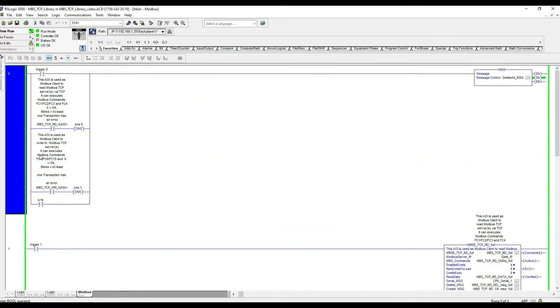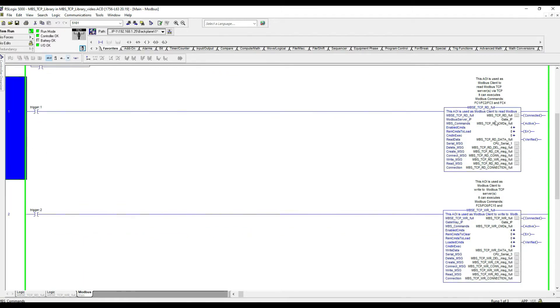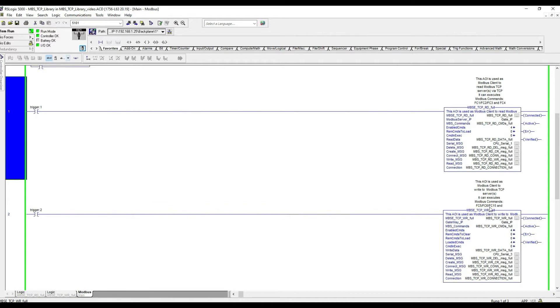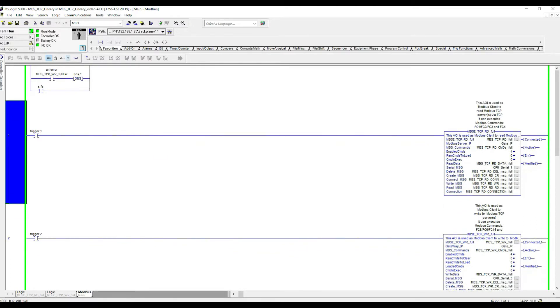In the PLC we have essentially three rungs. The first one helps us resume communication in case of errors. Then we have two add-on instructions that allow us to communicate Modbus TCP from our Allen Bradley PLC. The first one handles reads — functions 1, 2, 3, and 4. The second one handles writes — functions 5, 6, 15, and 16.